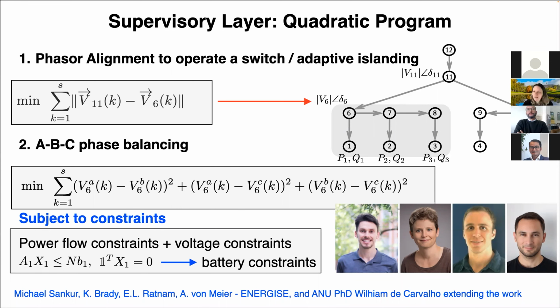Anyone want to come off mute if they know of any issues with voltage because of the unbalanced nature of the grid? If you have customers connected to a single phase, you have to be very careful about rotating that single phase those customers are connected to. Otherwise you could have an unbalanced system, and that unbalance could drive network expansion if not adequately balanced. Is that something anyone's aware of as a particular issue in the country?